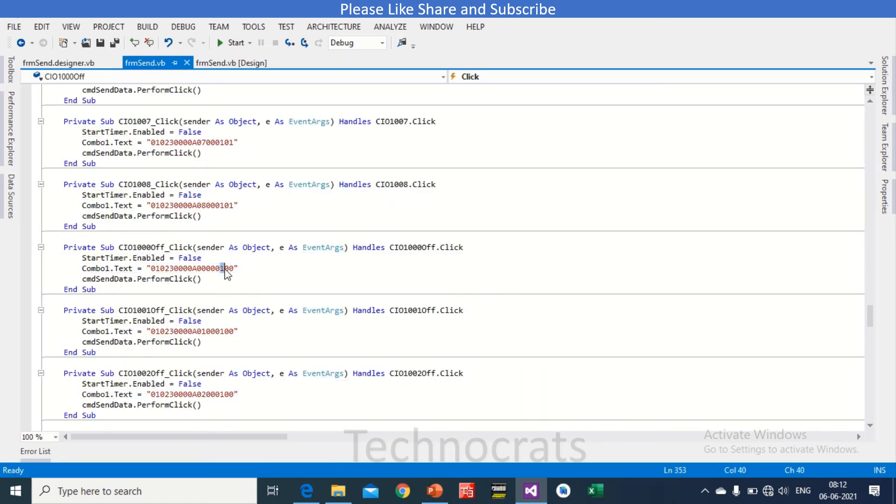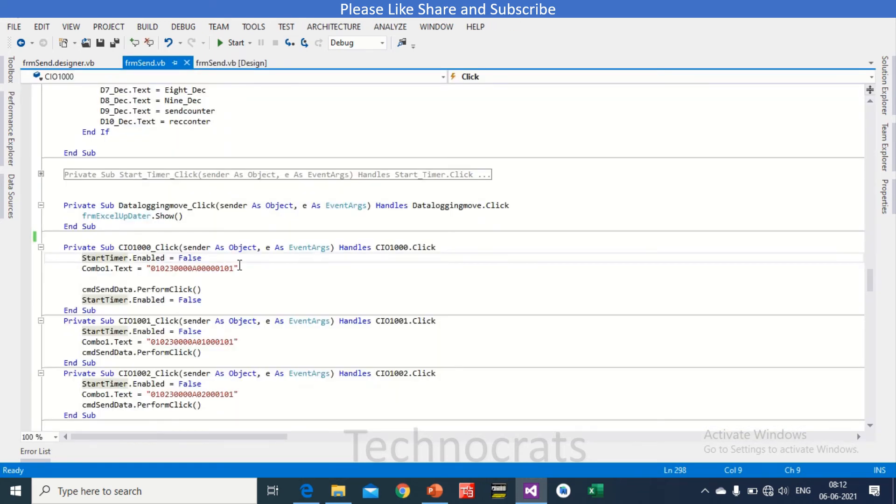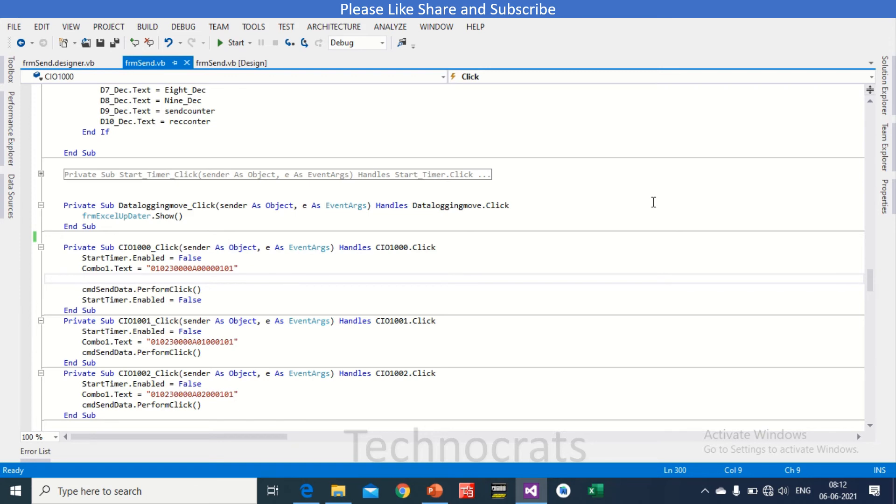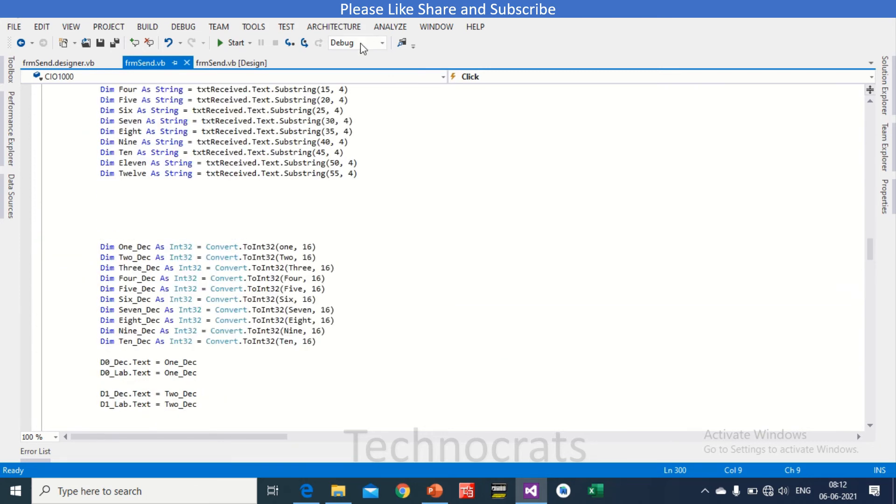If I write 00, then it will be set as 0, off command. Like, you can see here in off command, 01 01 01 and 00. But if you turn this, you are turning this 10.00 is on, then you can see that we have used 01 01. So this is FINS command for CIO write.